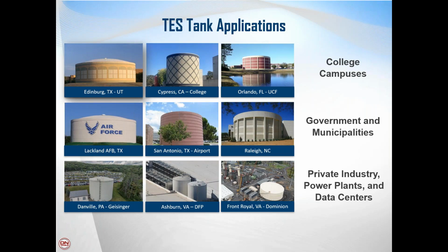Okay. And then the last question here. So to make a system complete, doesn't a set of pumps and a valve tree need to be added and thus maintained, albeit they may appear insignificant against the price of the tank? Yes, in some cases there is a separate pumping arrangement specifically for the thermal energy storage portion of the tank. That is true, but not in all cases. There are some systems where the tank is incorporated and there are no additional pumps required. There's additional valving required inside the central plant, but not additional pumps.